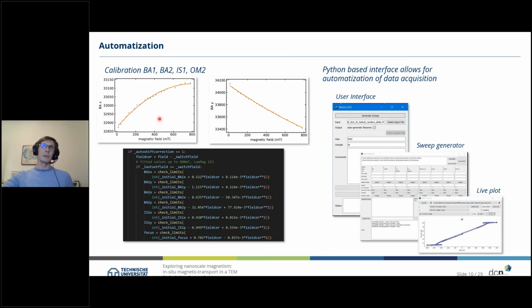And if you do so, we ended up with functions for the different shifts and tilts and defoci. We saw that this can be nicely described by polynomials up to second order, so either linear or quadratic, with different coefficients as a function of the magnetic field. And having these calibration curves, using a Python code we can apply any magnetic field and directly compensate shifts and tilts and defocus of our lens system to have stable imaging conditions for our different field sweeps, for example. All that is integrated into a Python-based user interface where you can put in sample name and so on.